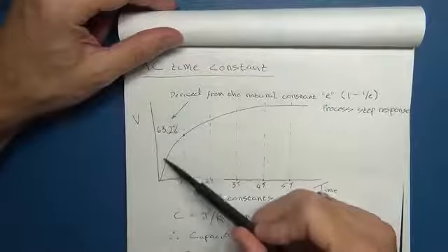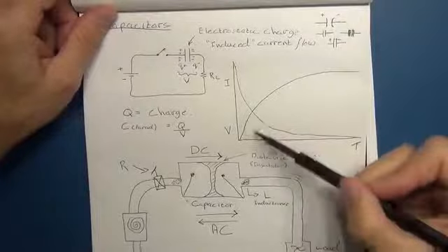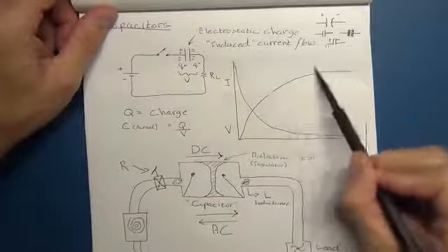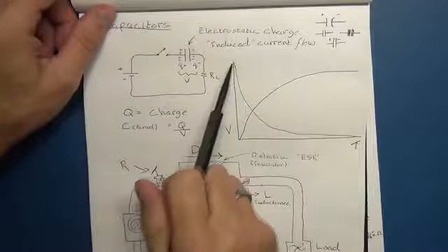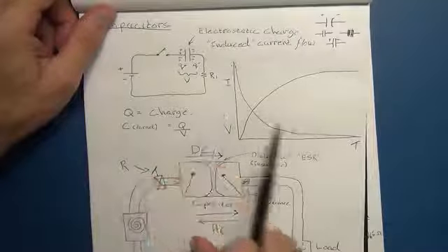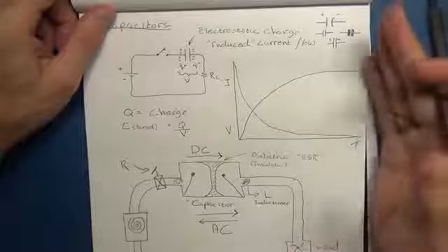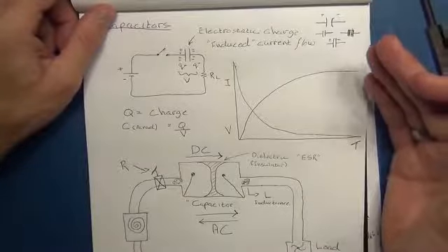What I want to show in this next demonstration is, for one, this charge curve. If we have a look back here at these curves, what I want to demonstrate is this charge curve as the voltage builds with a DC load, and how the current initially starts off high and then drops off, and then current flow is blocked. So we'll do a demonstration on that now.